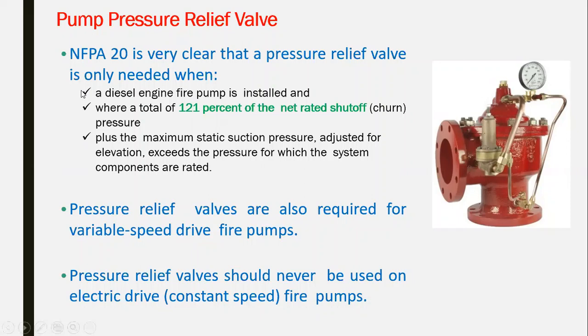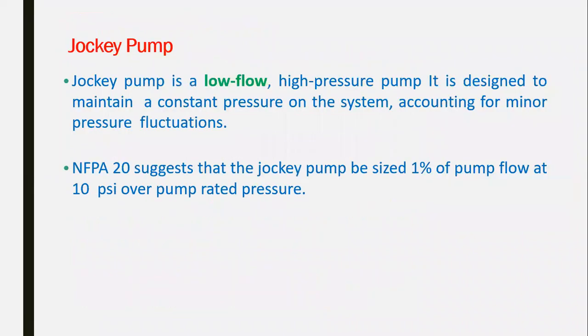And this one is required when a diesel engine pump is installed for a total 121% of net rated shutoff or churn pressure. So this one is working and relieving the pressure at 121% of the rated shutoff pressure. Okay. A relief valve should never be used in an electrical driven or constant speed fire pump, because this one is working with a diesel pump.